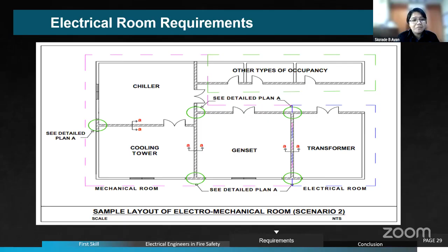So, paano kaya itong fire rating na to na required ni Fire Code? It's actually we are guided by Table 52, the fire resistance standards, which requires na kailangan natin ng 2 hours, at least minimum 2 hours of fire resistance rating for these walls between our generator, between our transformer, and between other mechanical rooms.